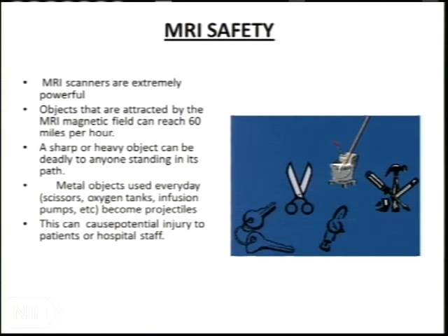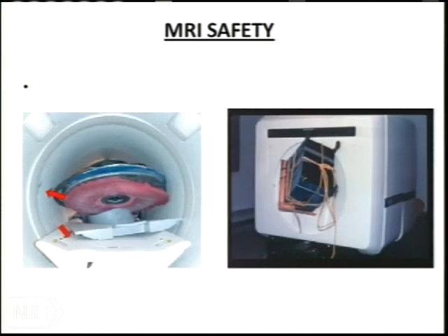So the technologists who run these scanners are absolutely trained to make sure patients don't walk in with anything metallic, healthcare workers don't walk in with anything metallic, and even doctors don't. And if you're not careful, stuff like this happens, like a buffer machine, because they were cleaning the room and they didn't realize that the magnet was on. The magnet is always on. Doesn't matter whether it's midnight, 3 o'clock in the morning, or 3 o'clock in the afternoon.